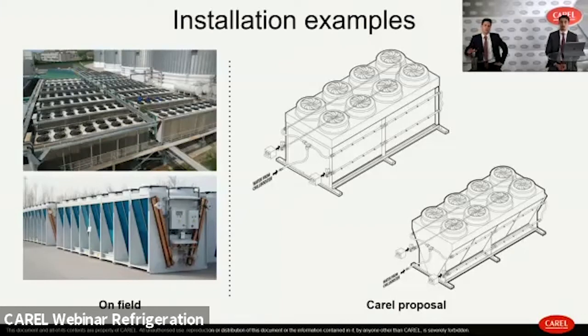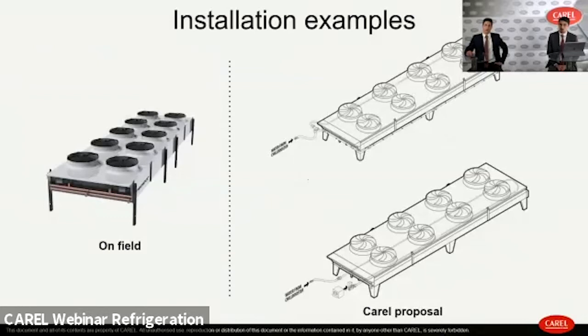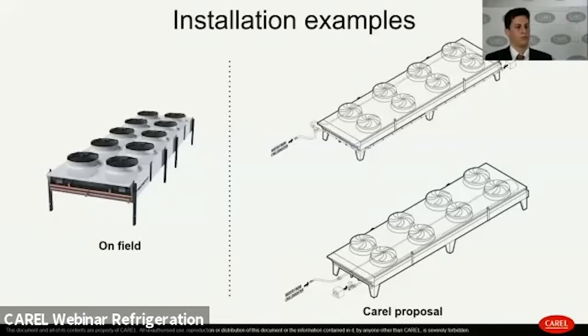In fact, not only vertical and V-shaped coils are suited for this installation. Also, horizontal coils can be suited. In this case we can have two kinds of possible layout. The first one is the so-called perimeter one. Manifold and nozzles are installed all around the heat exchanger, and this solution is suggested when the dimension and the water load are not big. If we have something bigger, we can think to move to surface distribution below the area of the heat exchanger.